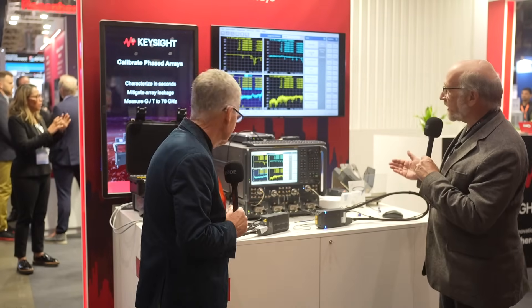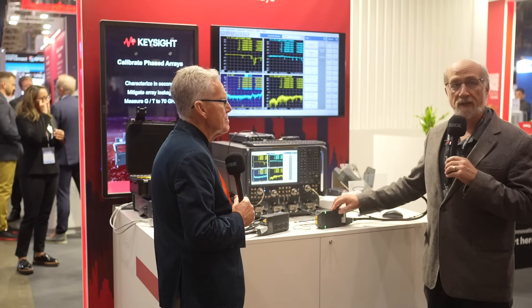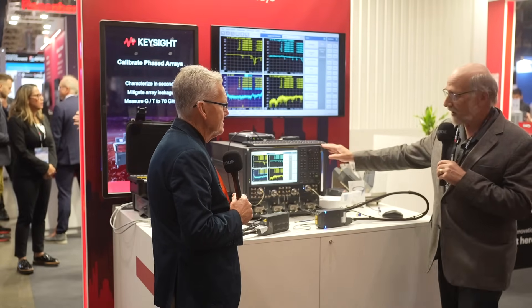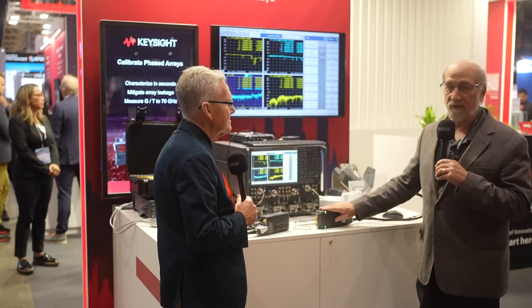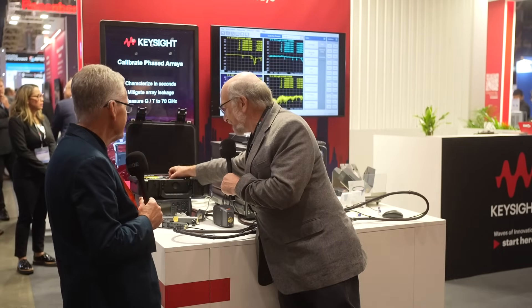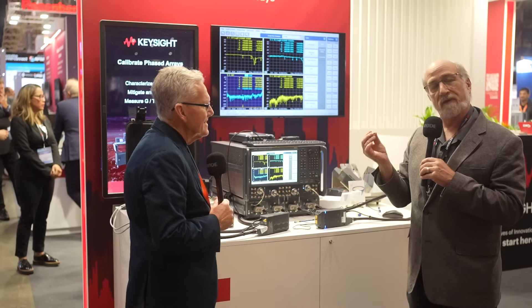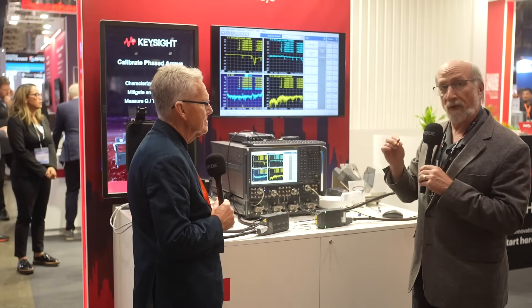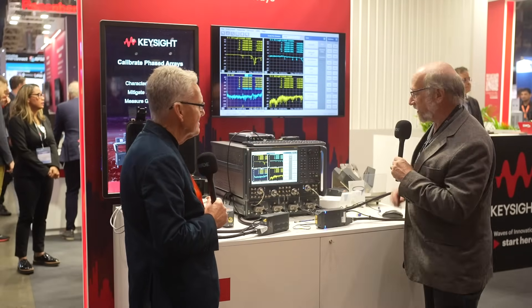What we're showing here today is our new Keysight 250 GHz network analyzer. These are extender heads to the standard PNA which extends it from 67 GHz all the way up to 250 GHz. To do that we had to invent a new connector. Here's a piece out of our calibration kit — a little piece of jewelry. This is one of our open, shorts, and loads with the 0.5 mm connector, which allows us to go all the way up to 250 GHz.